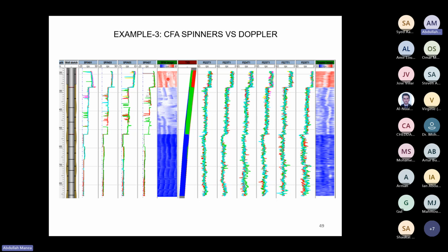This is the spinner image. Blue is low velocity, red is high velocity. And this is the Doppler image. Same, blue is low velocity, red is high velocity. And you can see that there is a very good agreement between the Doppler velocity and the spinner velocity, and Doppler confirmed that there is no significant frequency shift here. That means there is no significant change in velocity across this zone. We have a really good agreement between spinner and Doppler.